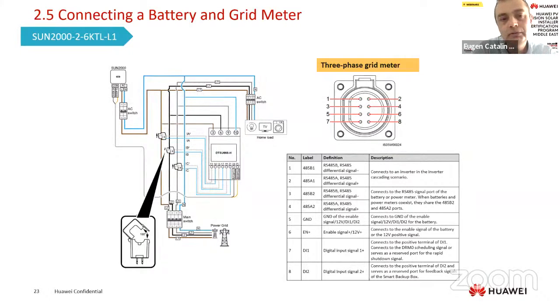On L1, we'll connect on position 3 and 4. I need to set a warning here for you. Do not install the meter in position 1 and 2, even if there is an RS485 communication. Position 1 and 2 is for the cascading scenario, to connect the inverters in a daisy chain between them. So the meter will be installed in position 3 and 4 only. If we have a battery, we'll connect it together with the battery in position 3 and 4.